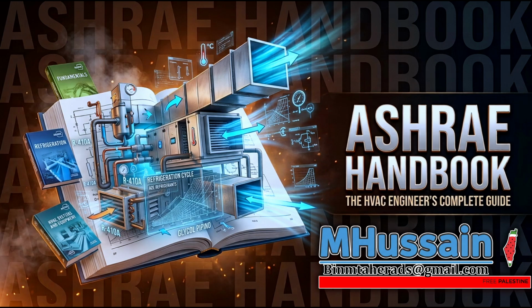It condenses back into liquid water, which engineers call condensate. Here's where the physics get dangerous: that high-speed steam can catch a wave of that liquid condensate, pick it up, and accelerate a solid slug of water through the pipe at highway speeds. And water doesn't compress at all. So when that high-velocity slug of water hits a valve, a sharp bend in the pipe, or a sensitive piece of machinery, it transfers all of that kinetic energy instantly, like a car crash. That is exactly what a water hammer is. It can blow out welded joints, destroy expensive control valves, and it's a severe safety hazard to anyone standing nearby.